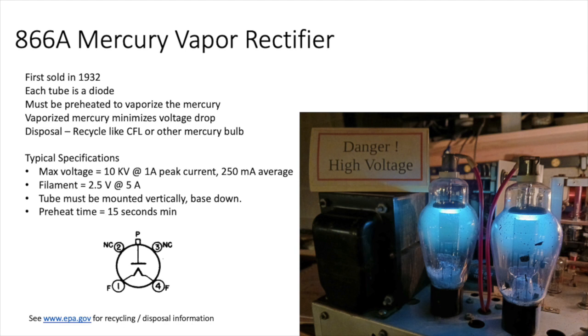Is there a time delay circuit to make sure you let the mercury vaporize before switching on? You have to pay attention to that yourself, watch the clock and wait 30 seconds or 15 minutes or whatever, using a timer, so you're using your own judgment to make sure you don't flip on the high voltage before it's heated up.